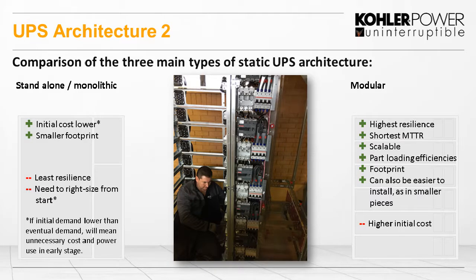Now, the other end of the spectrum is the true modular systems. Now, these have the highest resilience availability, typically have the shortest mean time to repair, and are scalable. So we can add and take away modules as required to increase and decrease the demands. The footprints are typically small, and because of the way they're modular, they can be very easy to install in small places. Now you see the picture in the middle is one of the systems we put into a hospital where the ability to take those modules out and reduce the size was able us to get that into a very tight, small space and still make it very serviceable in the future. But the downside, if there is one to that, is unfortunately the higher initial cost because you are paying for the multiple components and that flexibility.